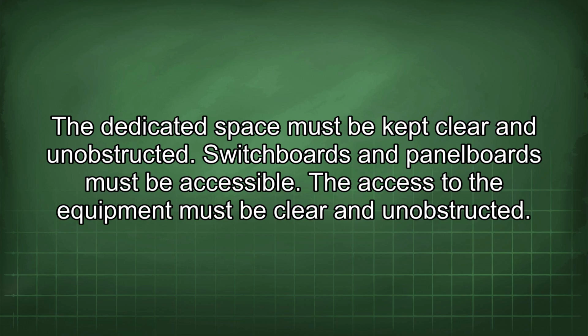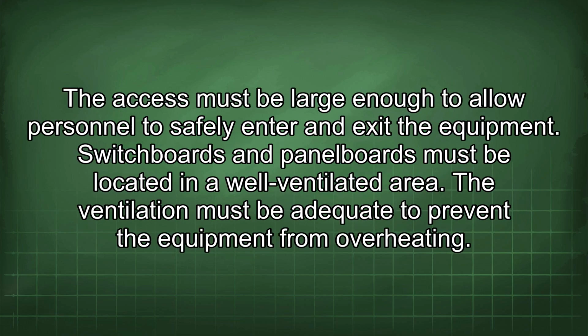Switchboards and panel boards must be accessible. The access to the equipment must be clear and unobstructed. The access must be large enough to allow personnel to safely enter and exit the equipment. Switchboards and panel boards must be located in a well-ventilated area. The ventilation must be adequate to prevent the equipment from overheating.